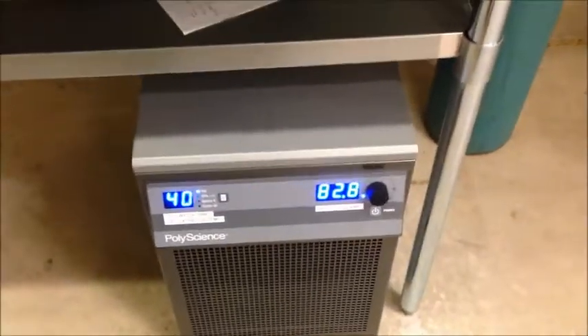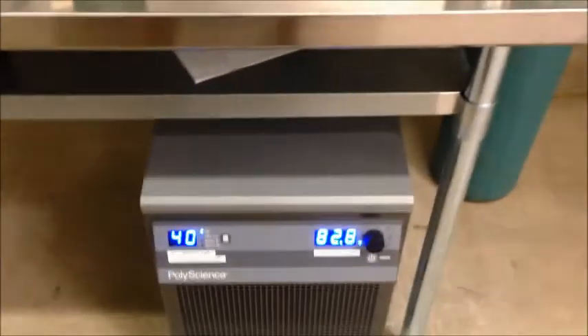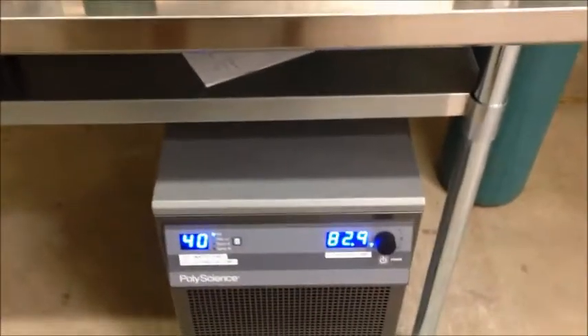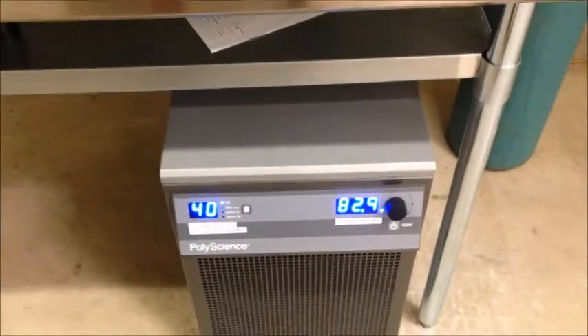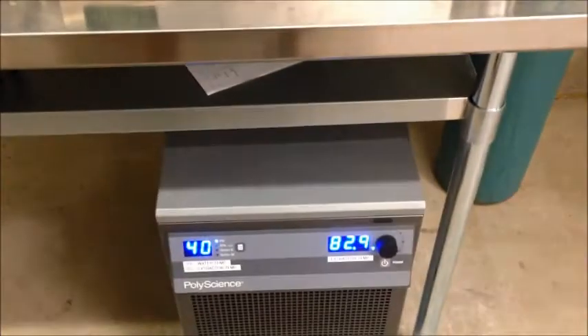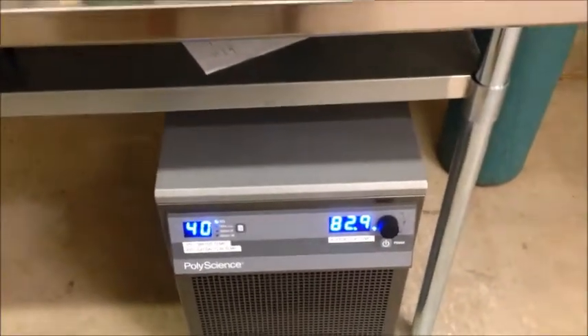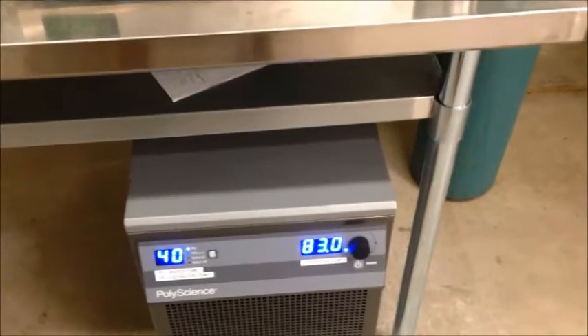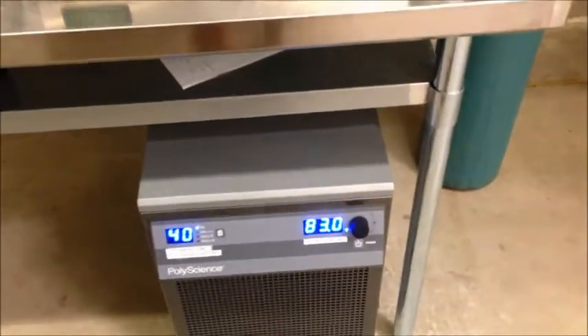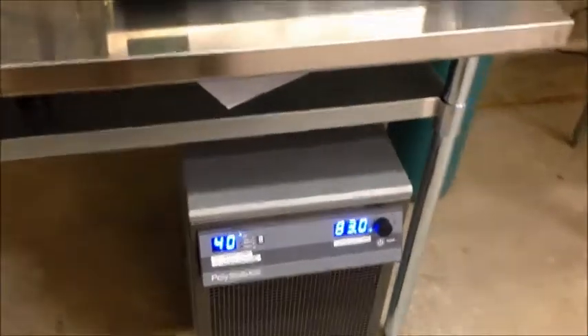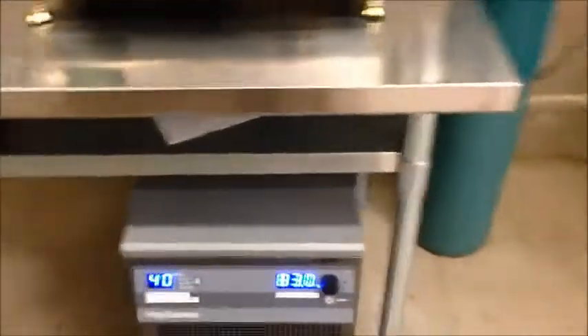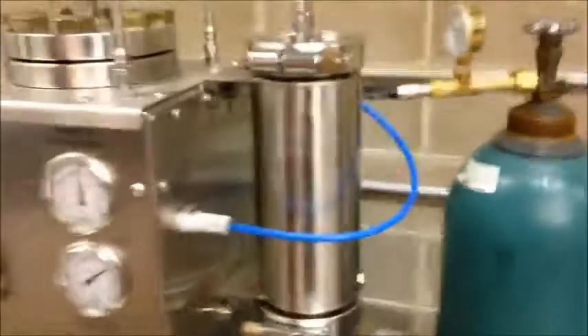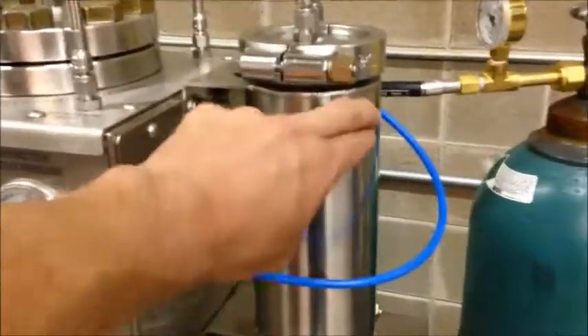During recovery, the manual recommends turning the chiller up to 110 degrees Fahrenheit to help speed up the recovery process. Some people don't like doing that because those higher temperatures will turn your oil darker colors. So if you like the lighter, more blonde, more yellow color, I would not recommend going over about 90 degrees on your chiller. Keep in mind, if you do not warm up your chiller, then it's going to be harder to get the oil out of here. It'll all be stuck to the walls.